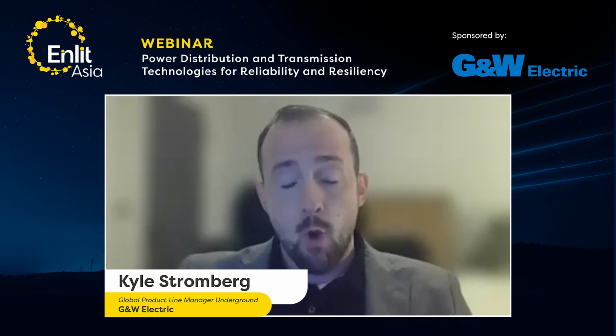If we're talking about hardening of the actual equipment, which is very important, some things I'd recommend utilities do when specifying equipment: one is to look at specifying equipment rated for outdoor conditions. Whether you're installing outdoors or indoors with risk of extreme weather impacting that environment, outdoor rated equipment can provide some major advantages.